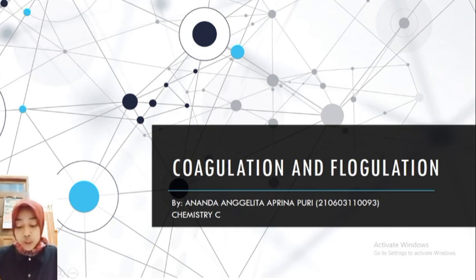Turbidity is also important. The lower the turbidity, the more difficult it is to form proper floc. The most common coagulant chemical used is aluminum sulfate, commonly alum. Alum works best in a pH range of 5 up to 7.